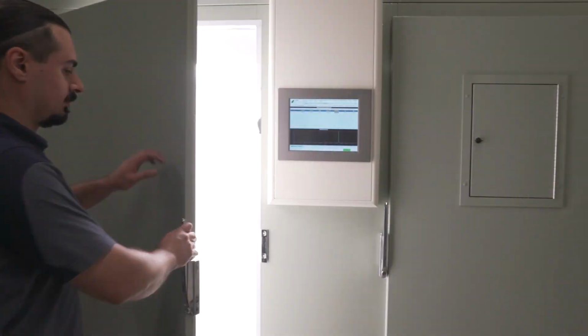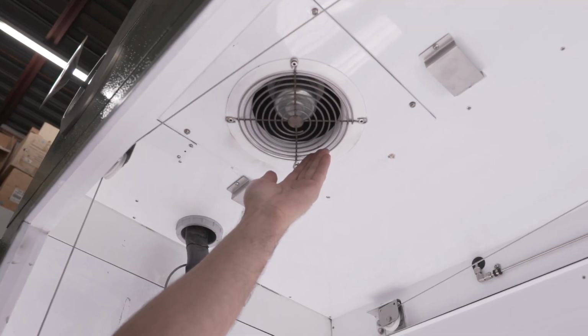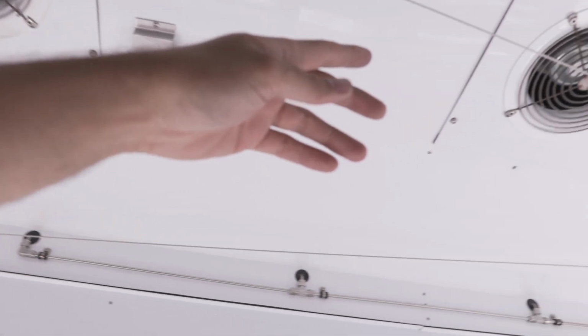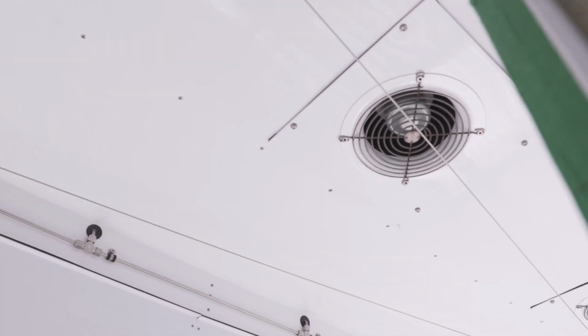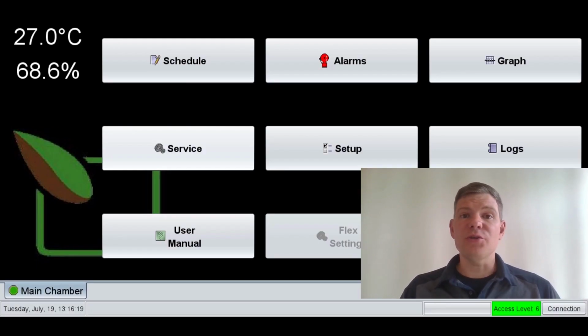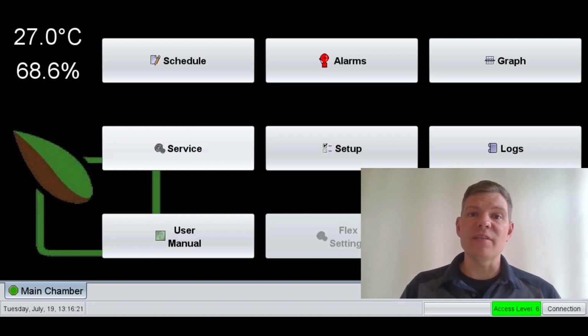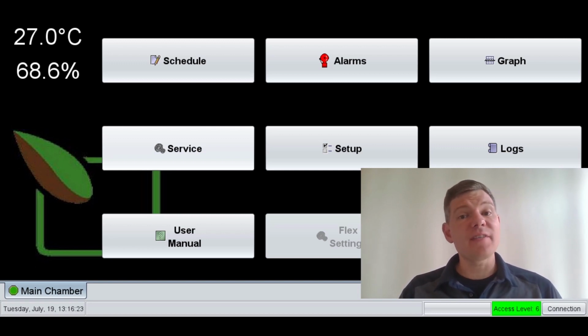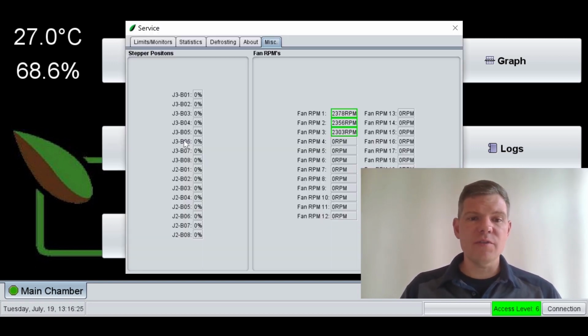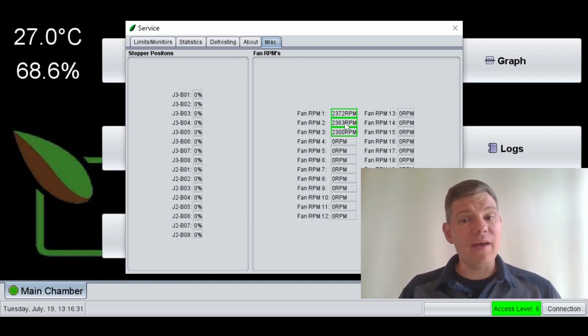Annual maintenance includes checking chamber air circulating fans, sensor calibrations, and the proper operation of high-low temperature limits. Newer equipment has circulating fans that can be checked with our VNet software. To check fan status in VNet, go to the Service area and Miscellaneous tab and look here in the fan RPM area. All active fans should be reading a similarly high RPM and be surrounded by a green box.